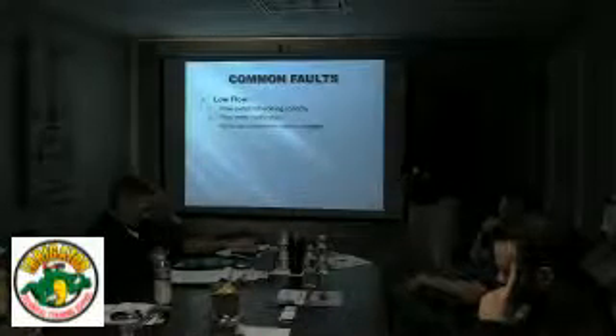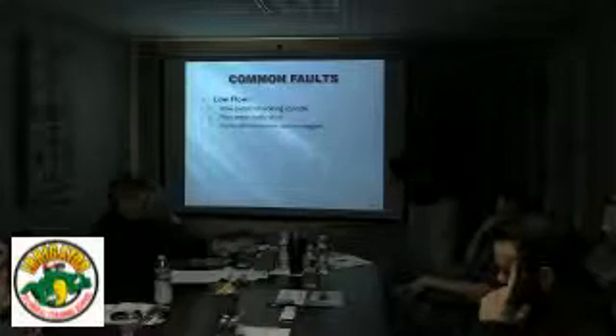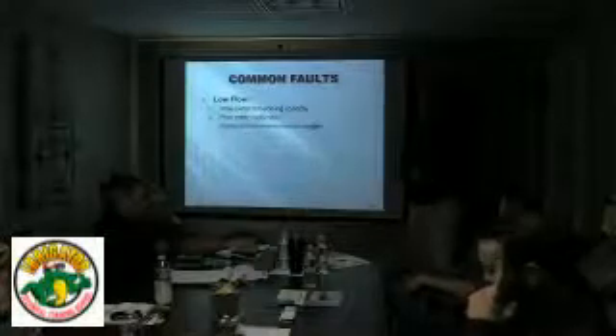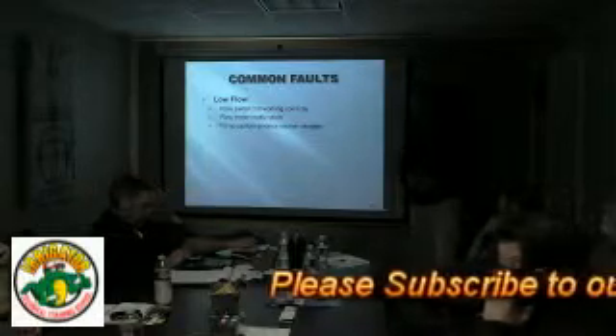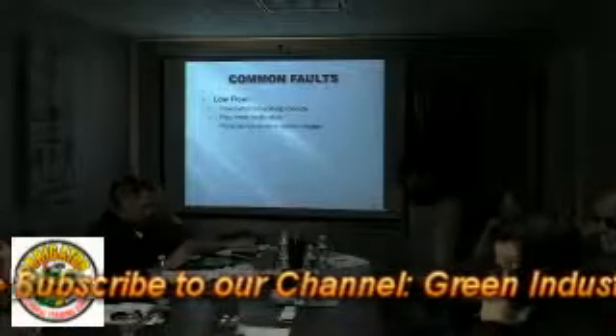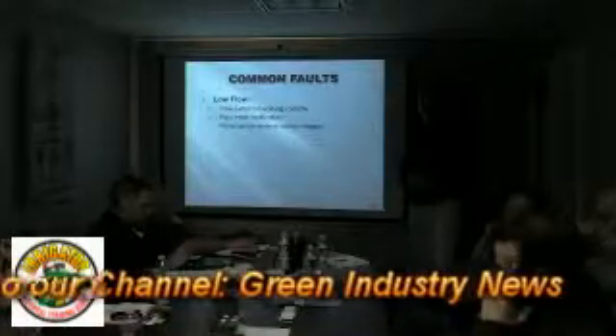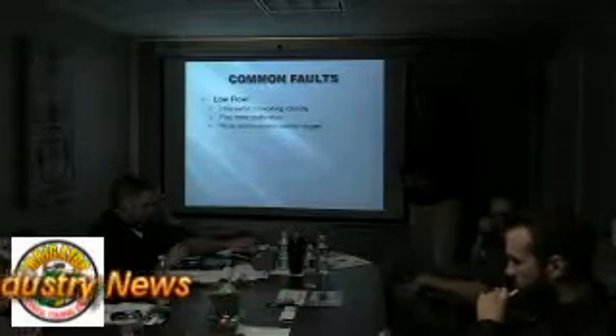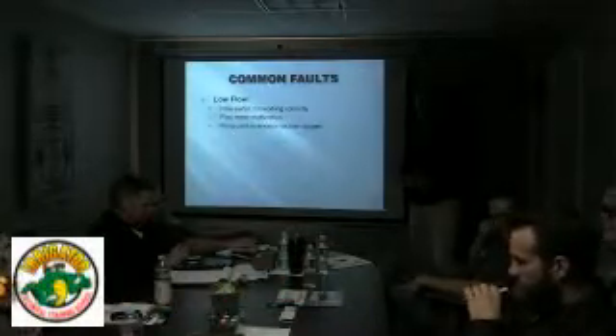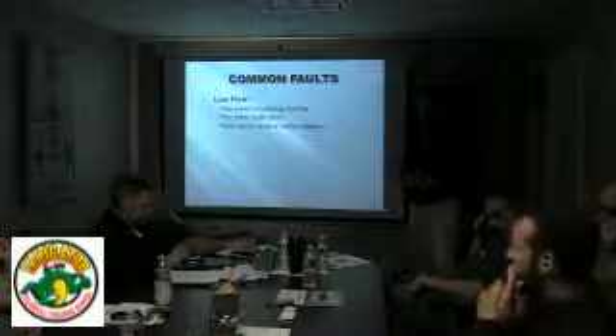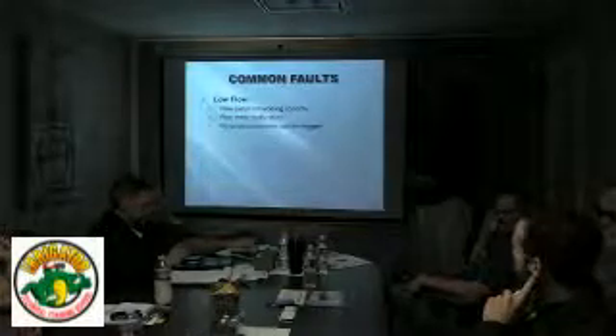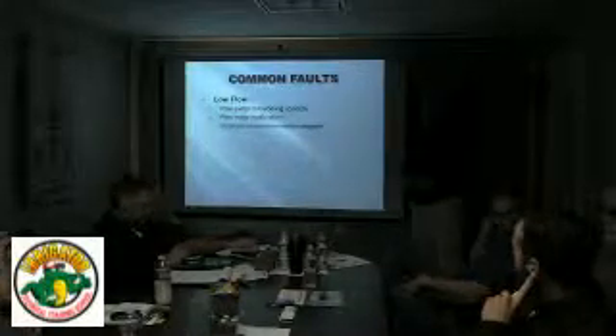So the low flow switch will sense that there's no flow, and then it will go through a time delay, and then it'll say, hey, we haven't had any flow for this long amount of time, and it'll shut it down. So it's mostly to prevent burning up your pump, overheating the centrifugal, or overheating the submersible motor. So once it's shut down, system pressure bleeds off due to leaks or whatever, does the pump restart again, or does it stay down? It takes a fault. If it faults on a low flow fault, you have to manually reset it.